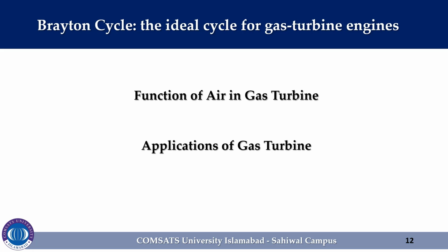Gas turbines are also used in stationary power plants to generate electricity, as standalone units or in conjunction with steam power plants on the high temperature side. In these plants, the exhaust gases of the gas turbine serve as the heat source for the steam. The gas turbine cycle can also be executed as a closed cycle for use in nuclear power plants. This time the working fluid is not limited to air, and a gas with more desirable characteristics, such as helium, can be used.